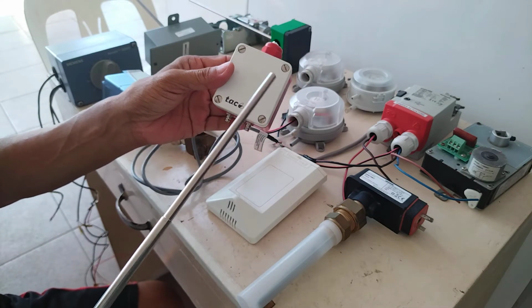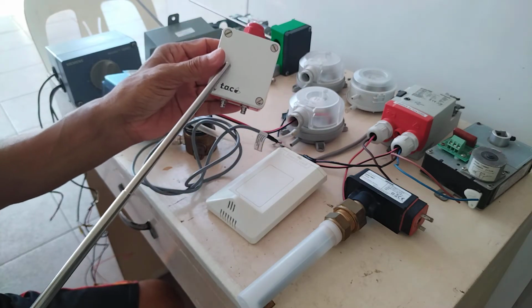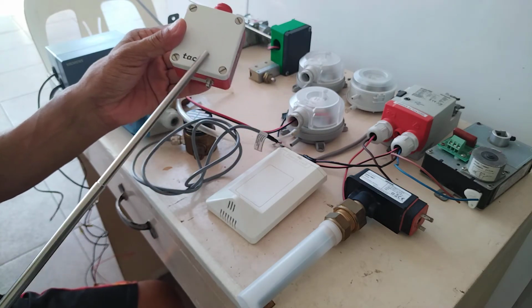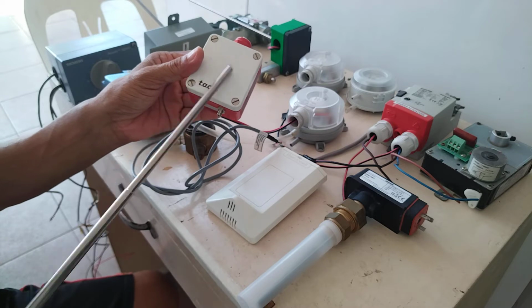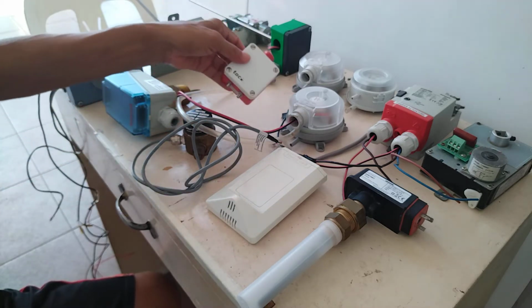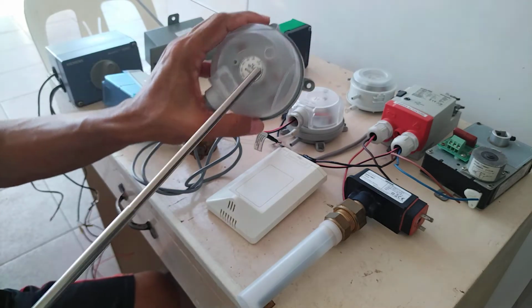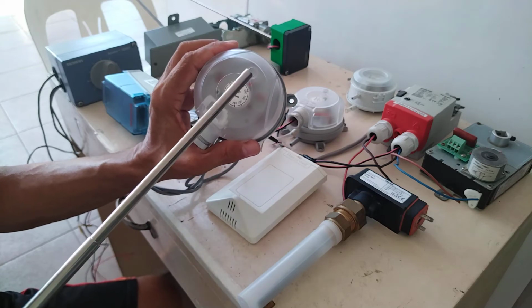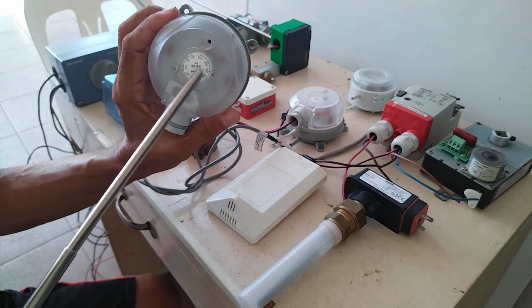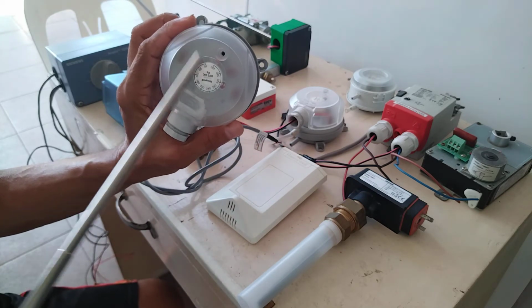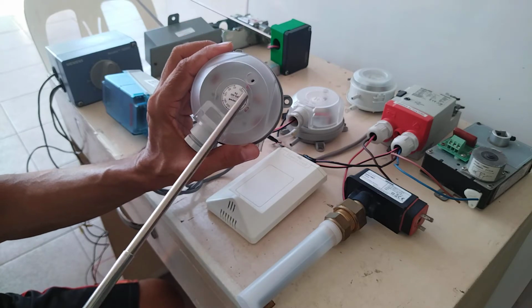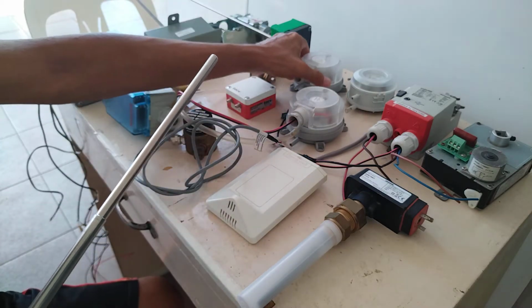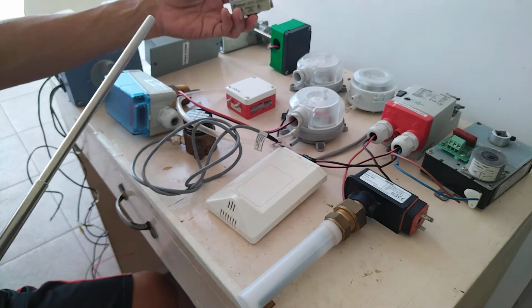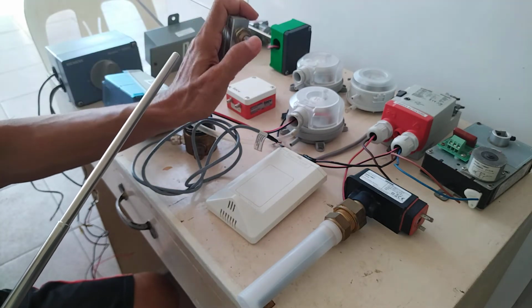So, there's a difference between a switch and a sensor. This one will tell you what differential pressure is being sensed. This one will just activate a normally open and a normally closed contact if the set point is reached. I mean, if the differential pressure set point is reached. Now, what I have here is a limit switch.